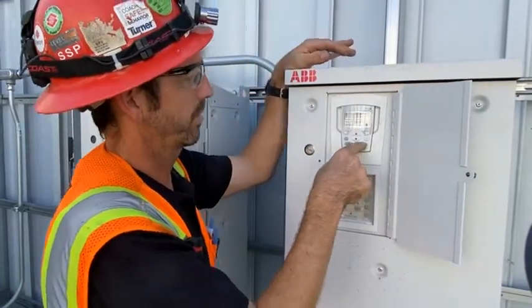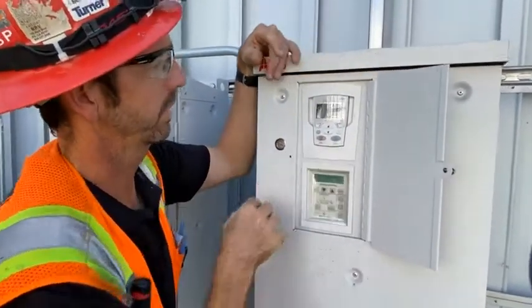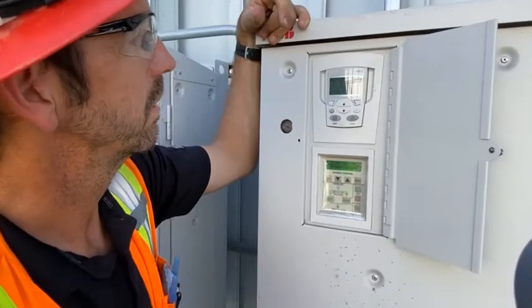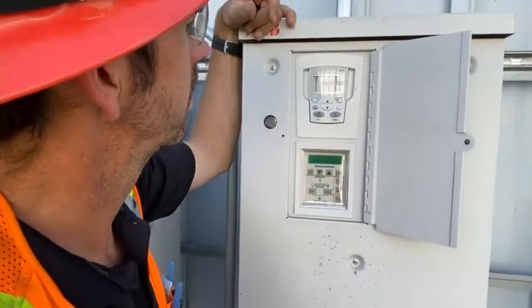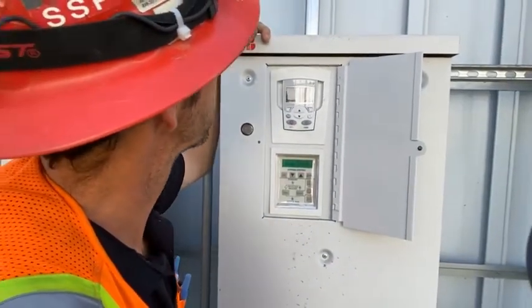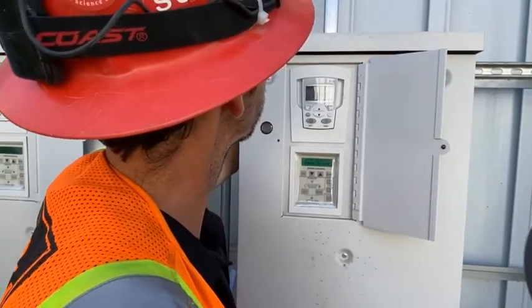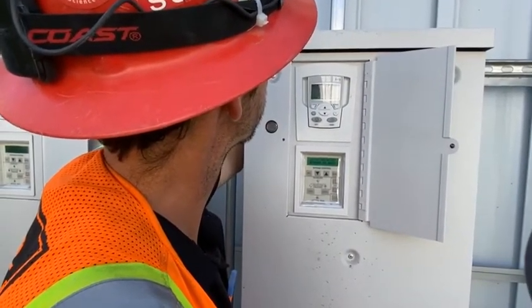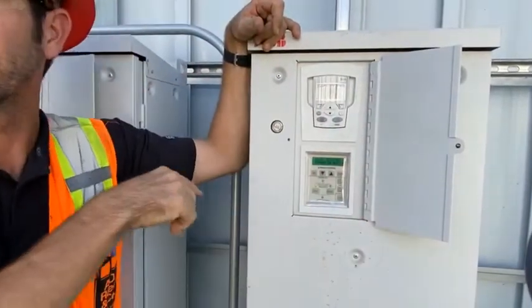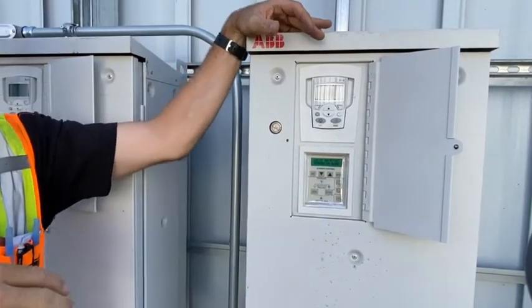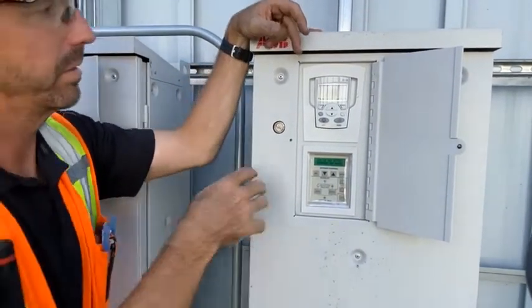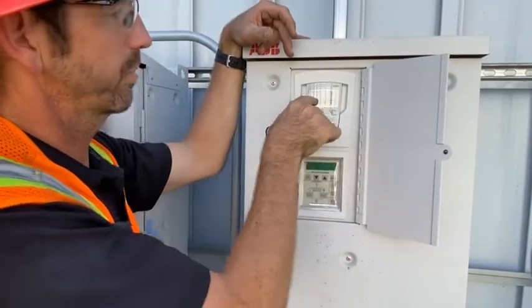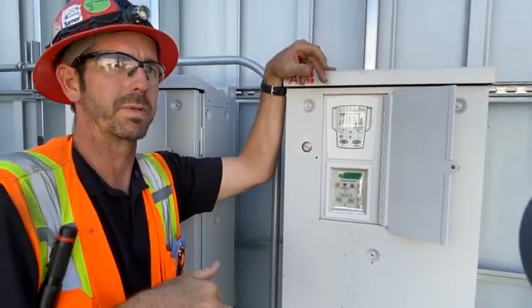And then now when the unit's running, I'll just turn it on in hand right now, it should go to 20 hertz. Okay, and now it's scaled properly. So if we would have gone to auto too, since there's not a speed reference signal, it'll go to 20 hertz too, which is our minimum program speed, okay?